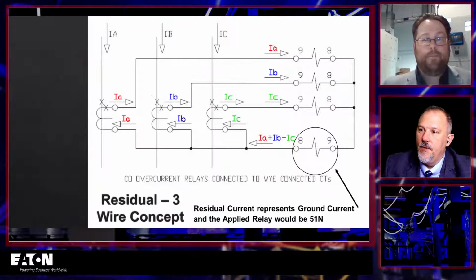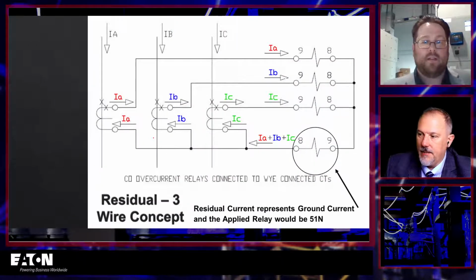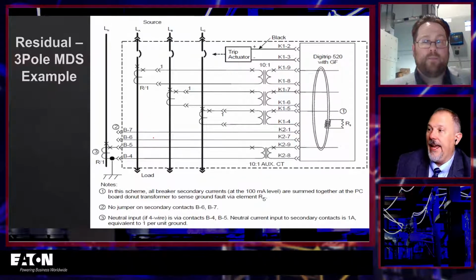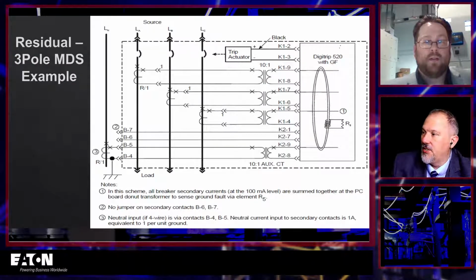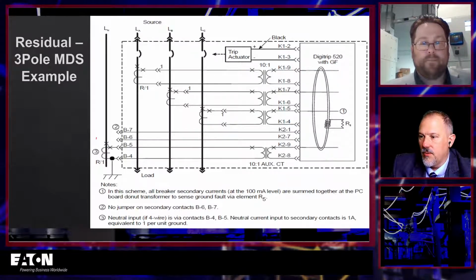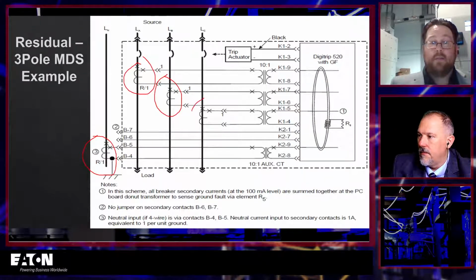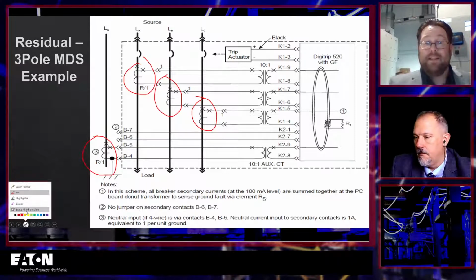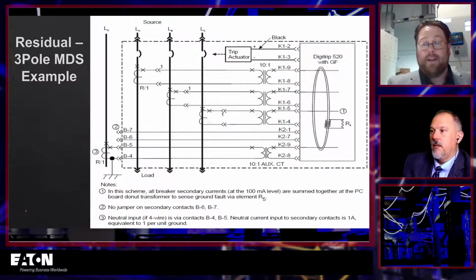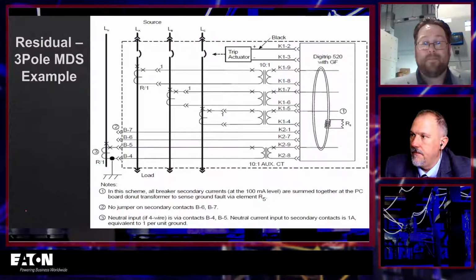And so this is your residual 3-wire concept. That's like a CO relay, and this would be what we do today in the Digitrip. And you're noticing, and it's exactly what I just said, right? So you do have this in the neutral here, right? So if you're doing residual and you have a 3-pole breaker, but it's a 4-wire system, that's really what we're talking about here. You have to have those CTs, the sensors, on all 4 wires. They're going to go to the trip unit, and the trip unit is going to do the summation. Yep. That's exactly right.